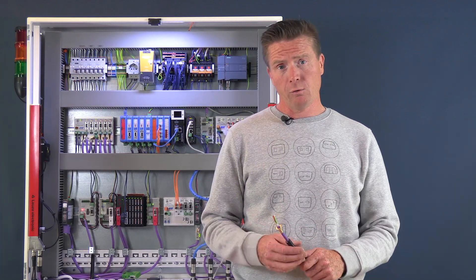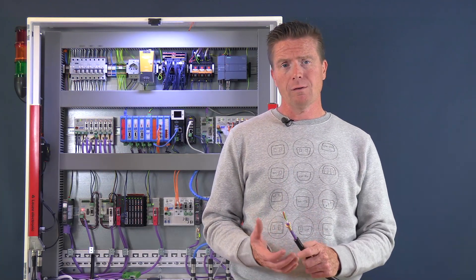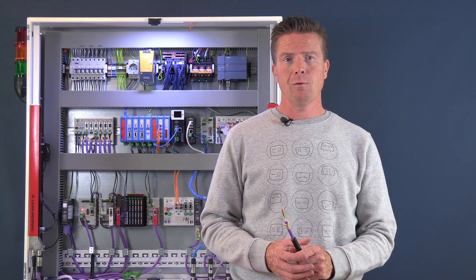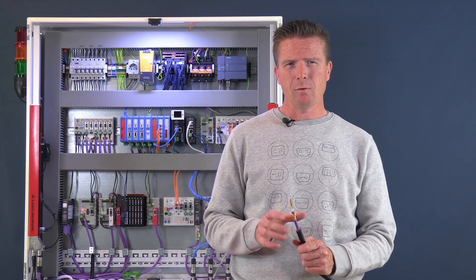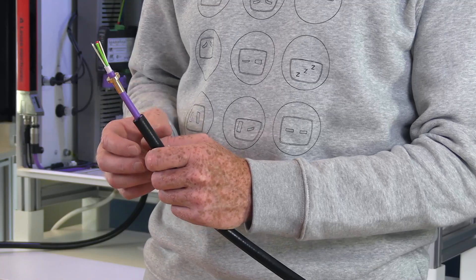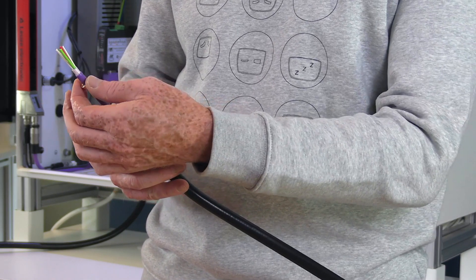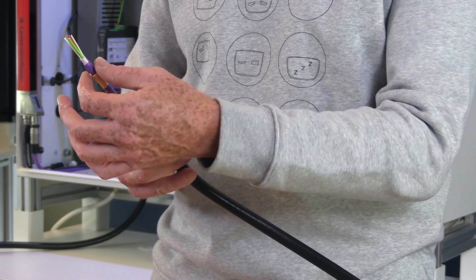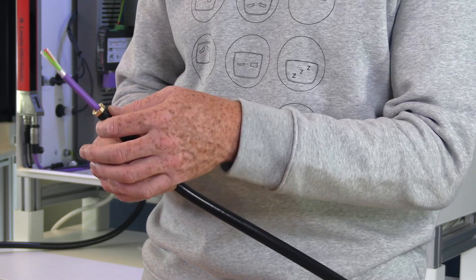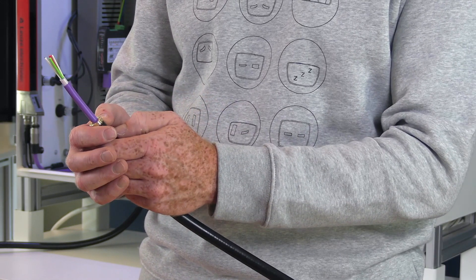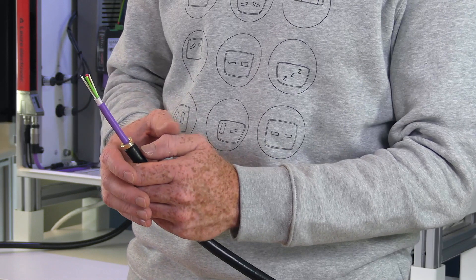Okay, I've got one more extra note. We also have another type of EMC Plus cable, and this cable is a little bit thinner. The Profibus cable is a little bit thinner. So what we did is you can slide over an extra tube to protect your purple jacket, so the copper tube in your EMC Plus cable will not cut through your Profibus cable.